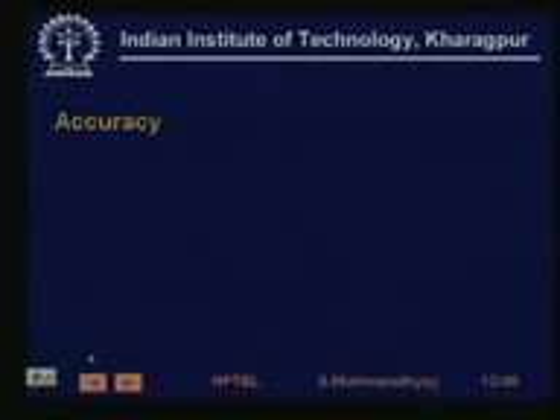Next, let's talk about perhaps the most important parameter called accuracy. If you see instrument specifications, they will generally be written as accurate to within X% of either reading or span. Sometimes they say reading, sometimes they say span. In fact, sometimes they also mention constant values, that is accurate within plus minus 1 degree centigrade. When it is a constant value, since the span is a constant quantity, you can always express it as a percentage of span also, right?